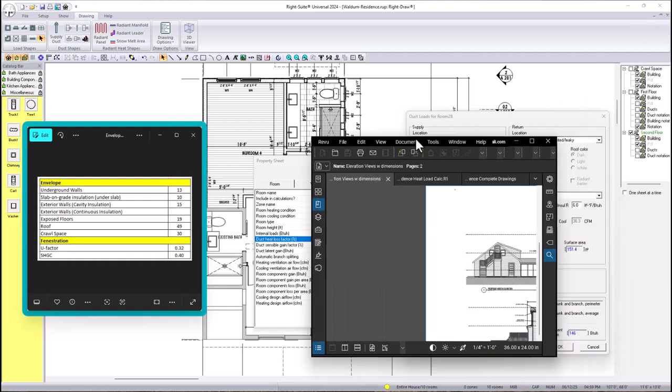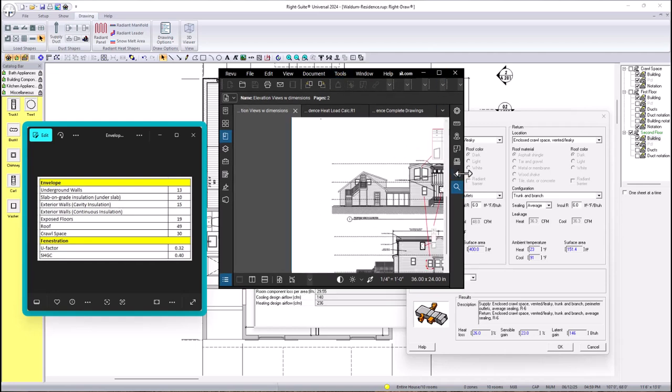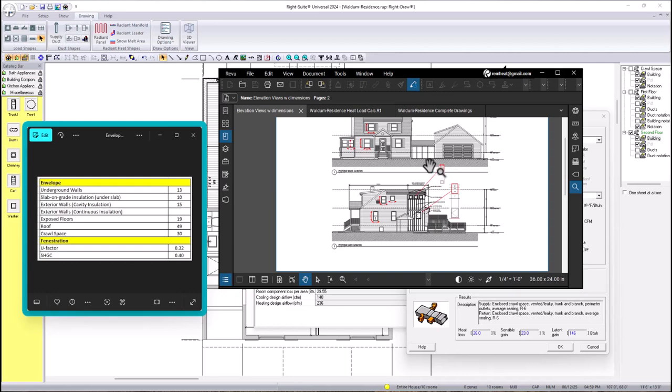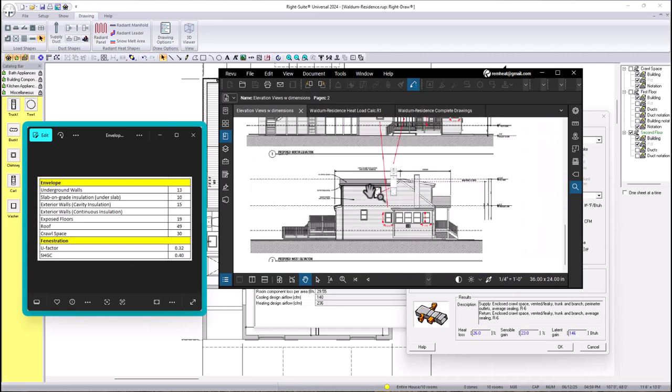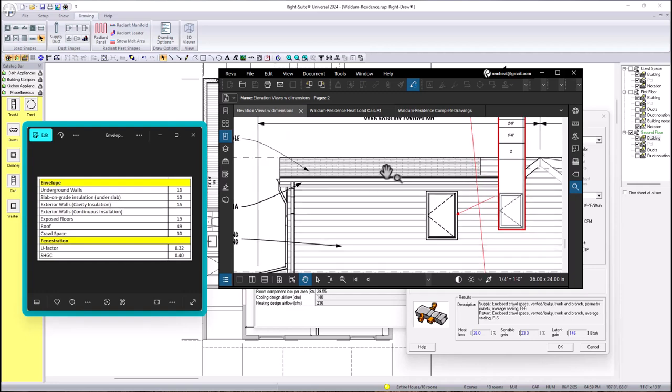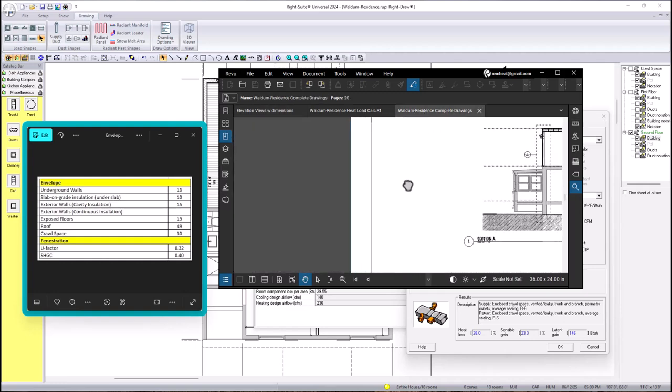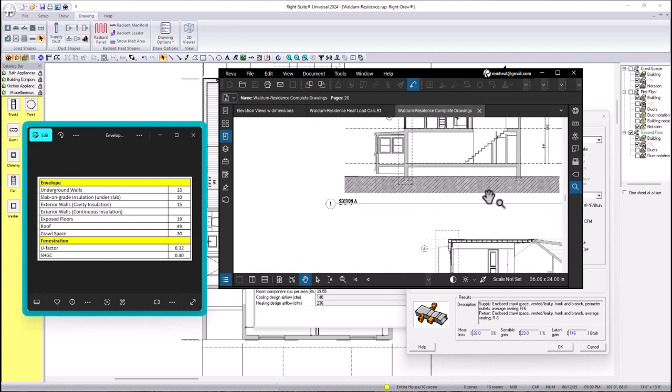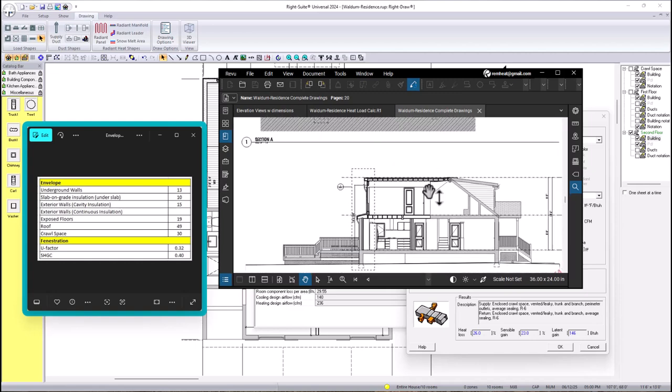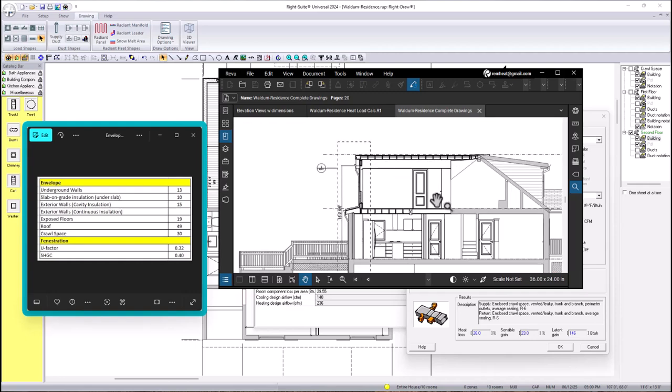So I'm gonna pull this to the side. So in here, as you can see, I'm gonna make it bigger. So let's make this. See, there you go. So there's not enough space for an attic in here. There's not enough space for equipment. There's no space for anything in here. But the way you confirm this is you check the other drawings, the section views. So this is the section of the building, orientation east. So in here, as you can see, I'm going to run the ductwork on the ceiling of the first floor because on the ceiling of the second floor there is no space.